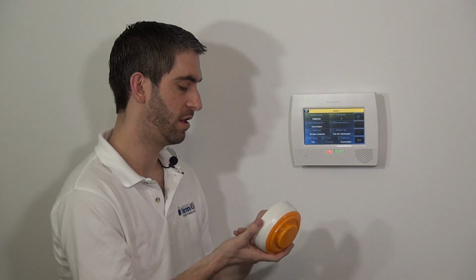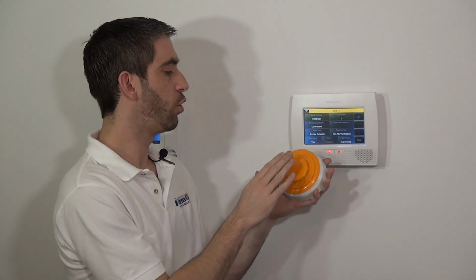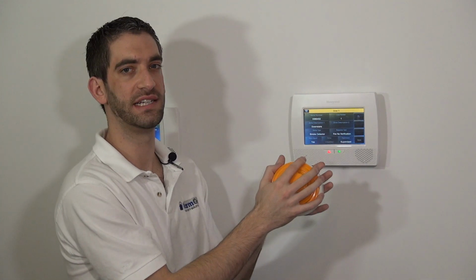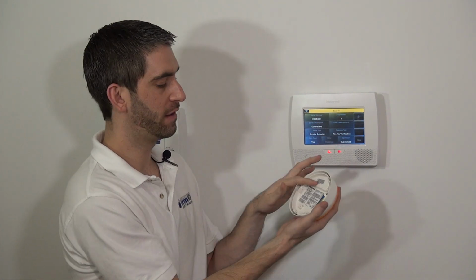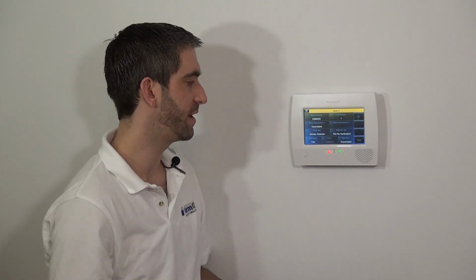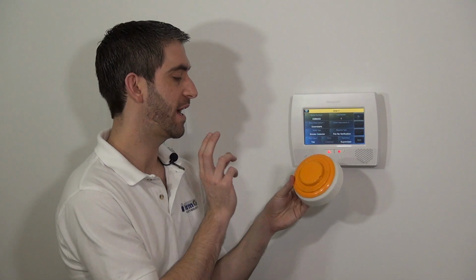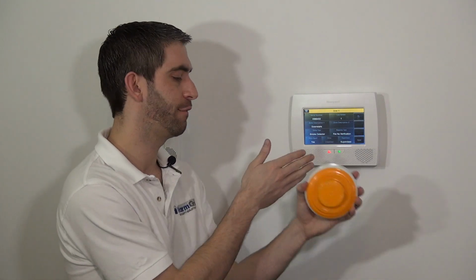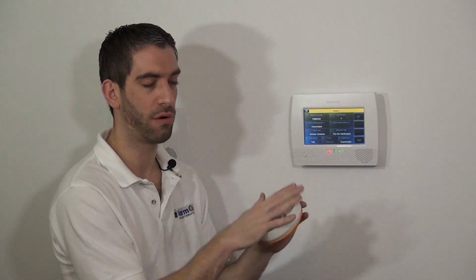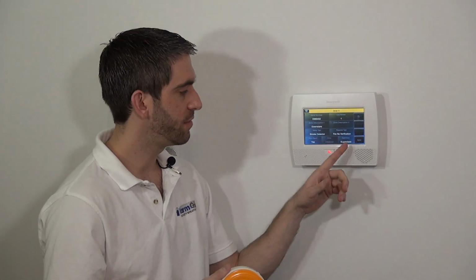Supervised, just like we've discussed on all of these sensor programming videos, means the panel will check for this device every 12 hours. And if it looks for the serial number and it's not getting the check back message from the device, it throws up a zone 11 smoke detector trouble, alerting you to an RF supervision problem. That could be that we put the wrong serial number in, it could be a range issue, maybe this is too far from the panel, or perhaps there's some interference preventing this panel from seeing the detector, which would indicate a problem, meaning that the detector may not be able to transmit the alarm to the panel. Or worse, if this unit was tampered with or broken, then of course the system wouldn't see it. So this 12-hour supervision check is important, and we always want to have it supervised.